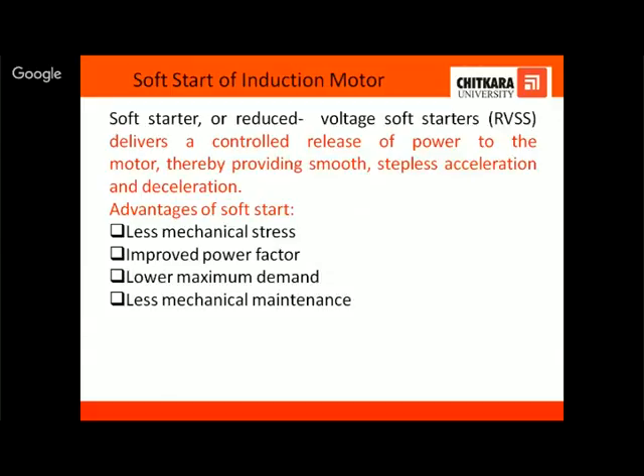Sometimes there are huge motors installed in the industry. When the motors are starting, say 2 or 3 motors are started together, there will be a high inrush current flowing in the system. It may happen that your maximum demand exceeds the predefined value, so that sometimes the electricity utility may ask for a penalty. Then it also requires less mechanical maintenance.